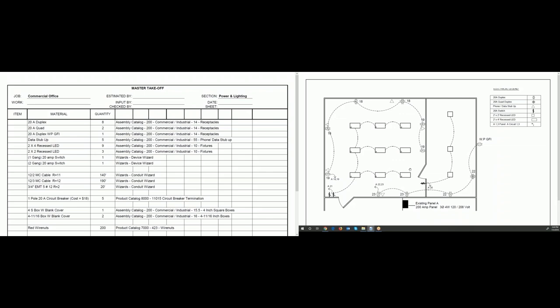You want to estimate as close as you can. Practice on a blank takeoff sheet — we provide one. Last point on conduit takeoff: you have a certain wiring method when doing electrical projects. In California, for example, we can't come out of panels with MC cable, so we have to stub up out of the panel with three-quarter EMT. We bring a three-quarter conduit up, over, and into the accessible ceiling space, set a junction box, and drop down to the nearest receptacle of that circuit.